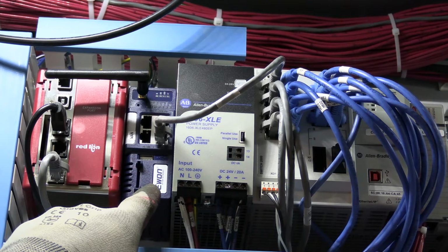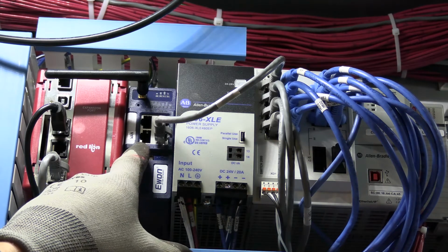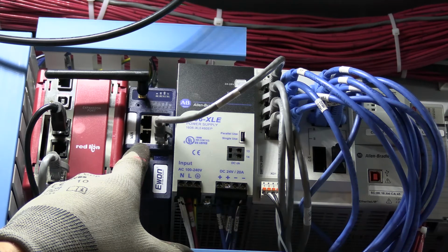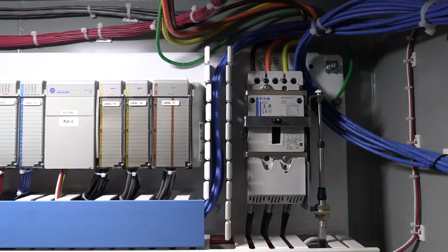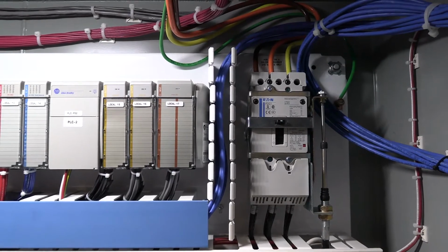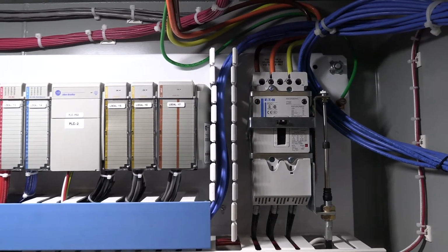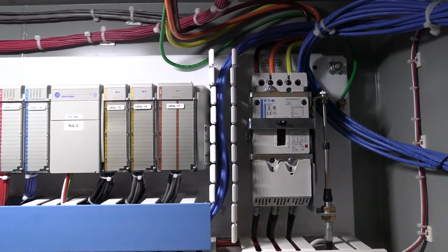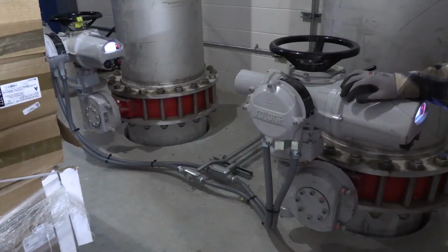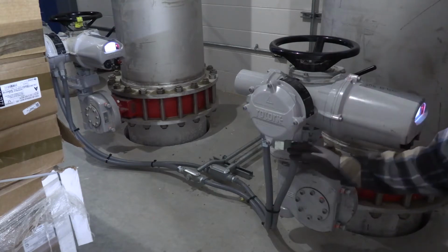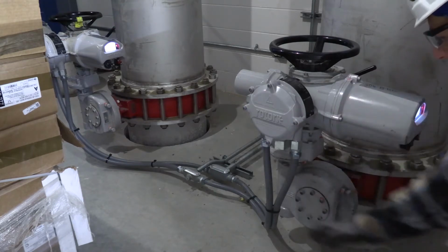And you can see the blue Ewon here. It is recommended that you provide an Ethernet cable with internet access to this E1 before startup. Lastly, please show a picture of the main breaker, clearly showing where the line side conductors are terminated on the breaker. An overall picture of the aeration valve is also a must. We must confirm the correct wiring and mechanical installation.